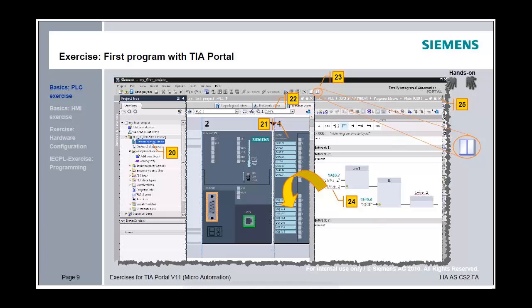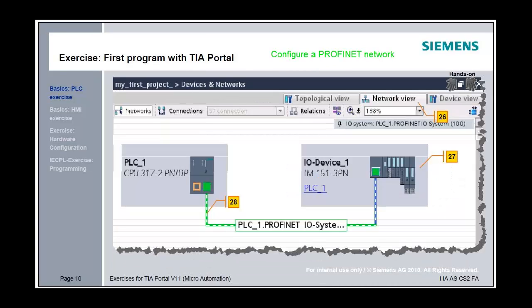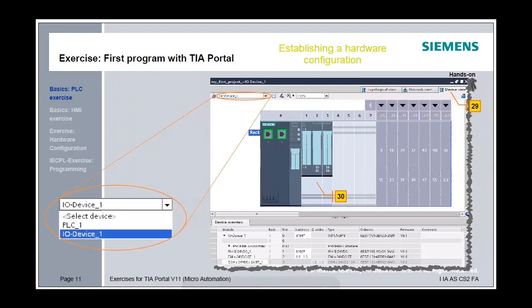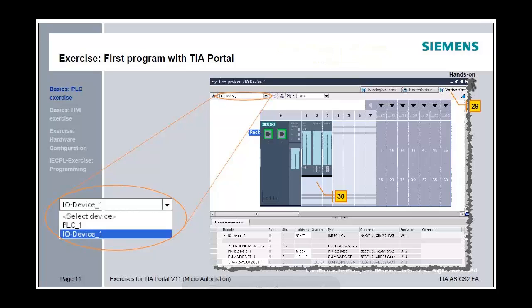Close the main view and change to network view. From the hardware catalog, add an ET200S PROFINET station. It can be found under Distributed I/O, ET200S, Head Module PROFINET. Change to device view and add from the hardware catalog one power module, one digital input module, and one digital output module.